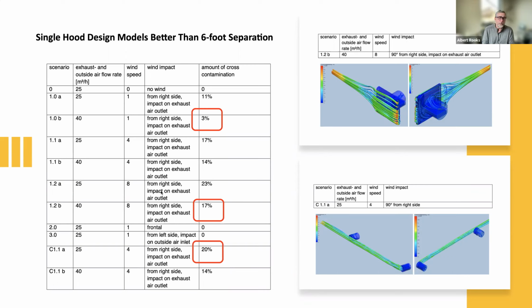Essentially what they did was fluid modeling, and they compared their hood, their single hood that divides the intake from the outflow all within the same hood. And it shows the pathway for both compared to 6-foot separation down below. And it's all about how much wind there is and what the wind direction is. But in the extreme cases, the upper columns there, the red circle that says 3%, in that case, with the airflow, the wind coming from the right side, and impacts on the exhaust output, basically has the potential of 3% cross-flow contamination.